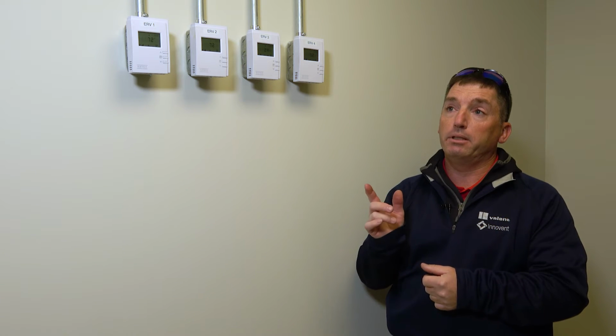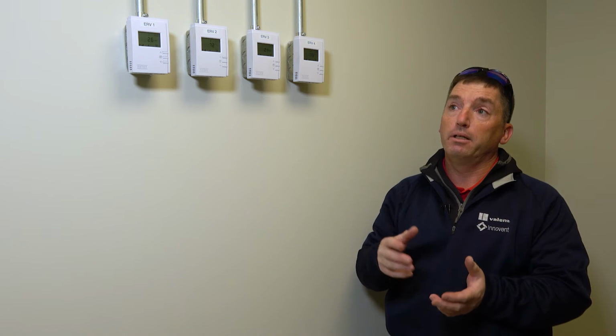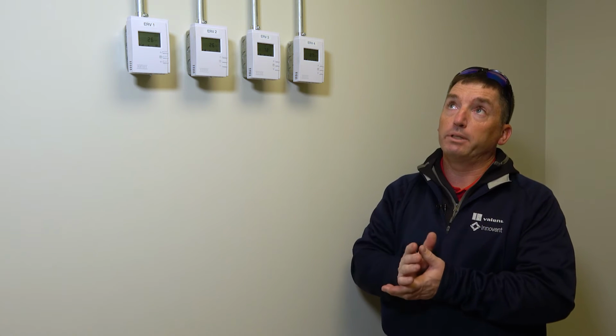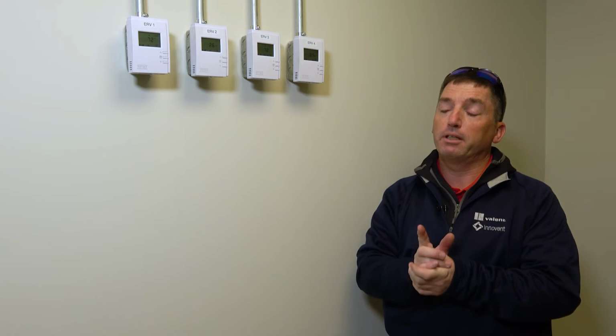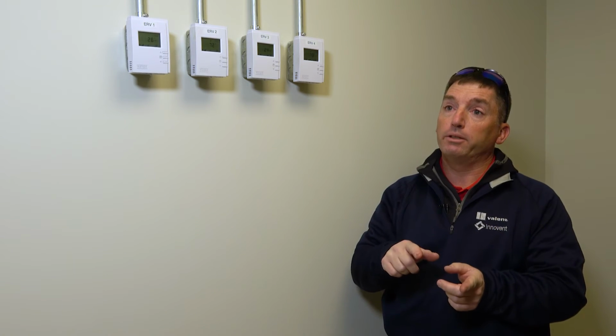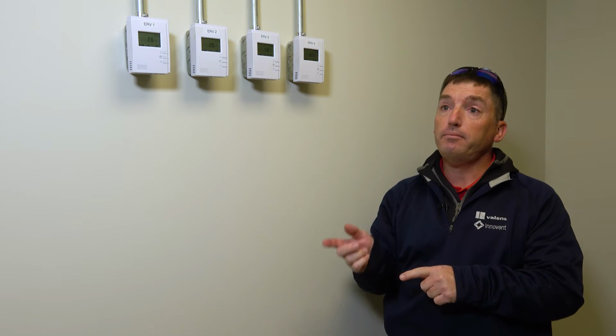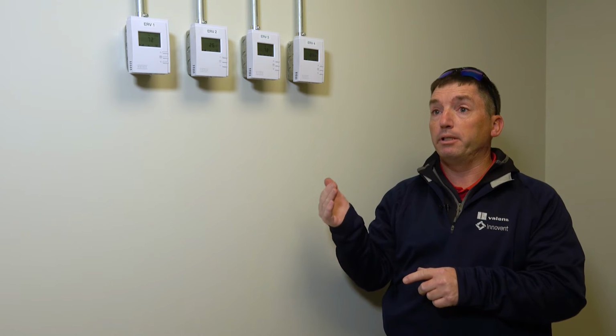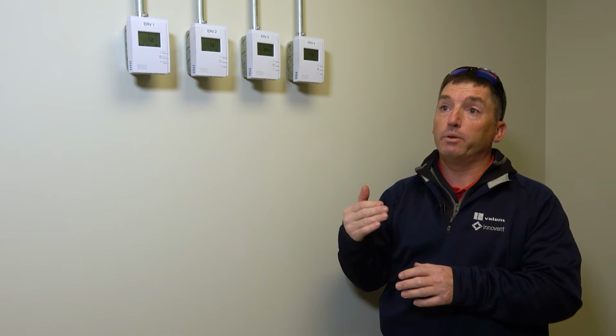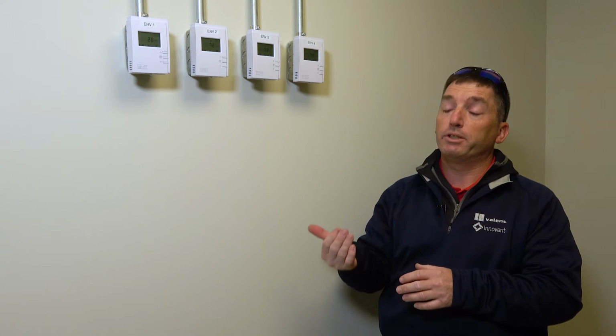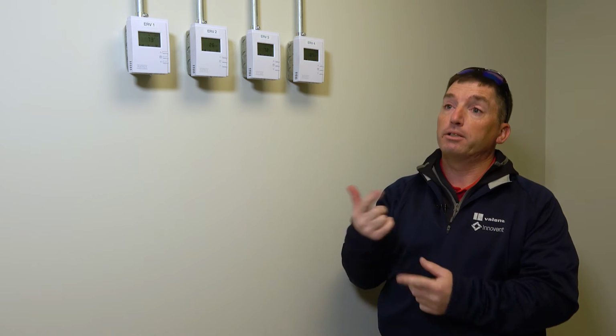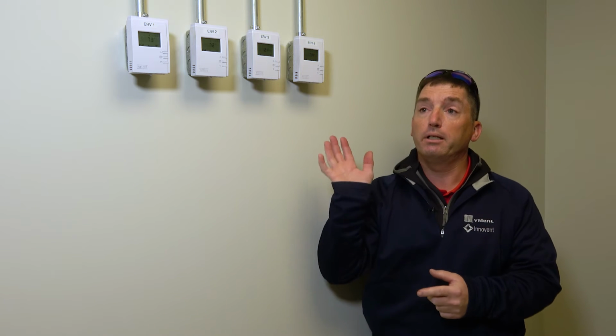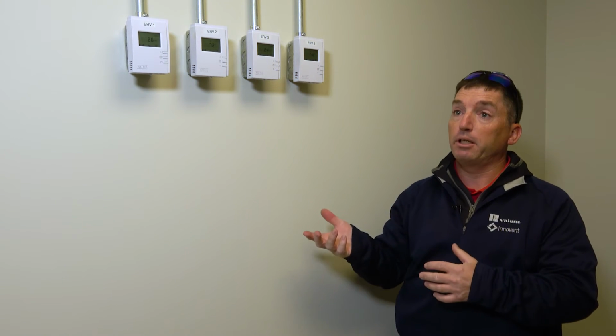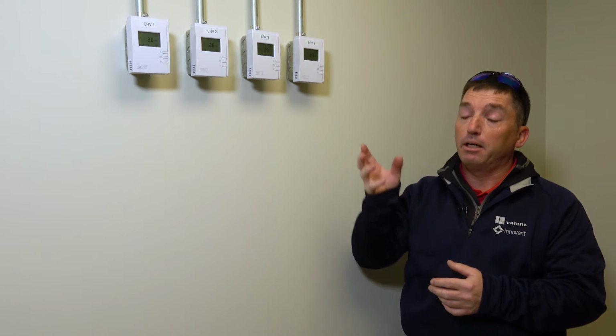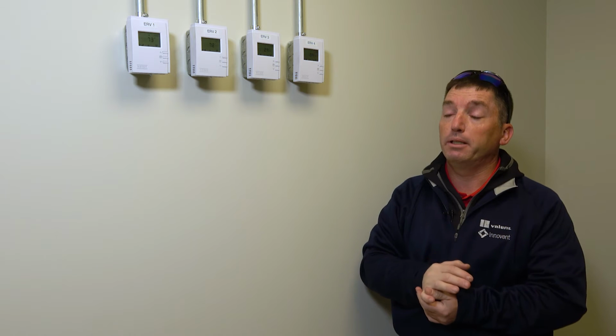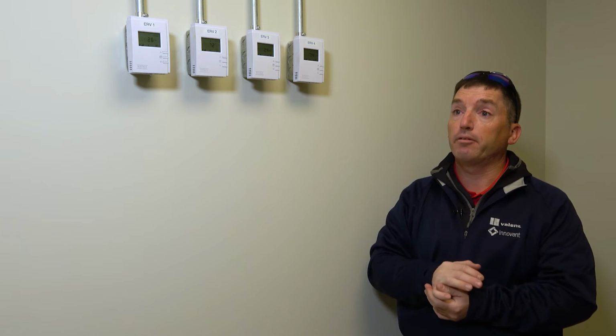The unit has a built-in functionality in the software that at an outdoor temperature, which I believe was set for 65 degrees, I can confirm, it's automatically going to change operating modes. So in other words, when the outdoor temperature is below 65, it's automatically going to disable cooling, enable heating. And once the outdoor temperature rises above 65, it's going to disable heating, go on cooling. So you don't really necessarily have to worry about enabling or disabling the functionality here. Like I say, there is an algorithm in the controller that is going to take care of that for you.